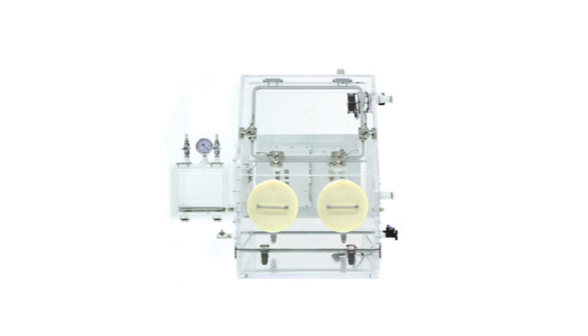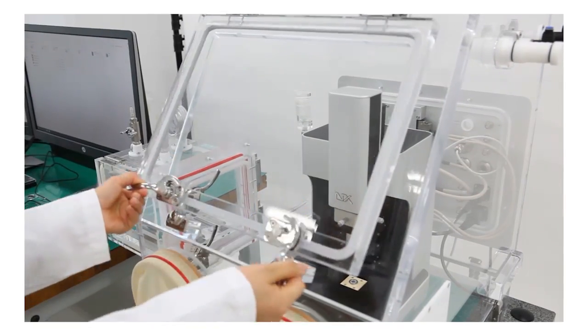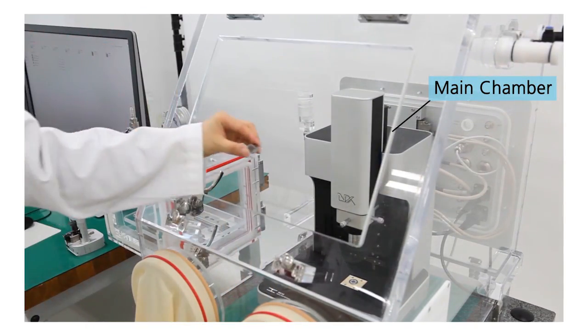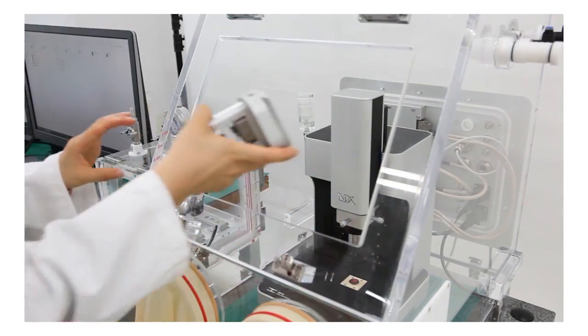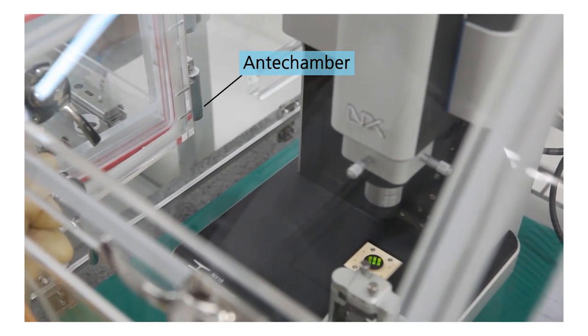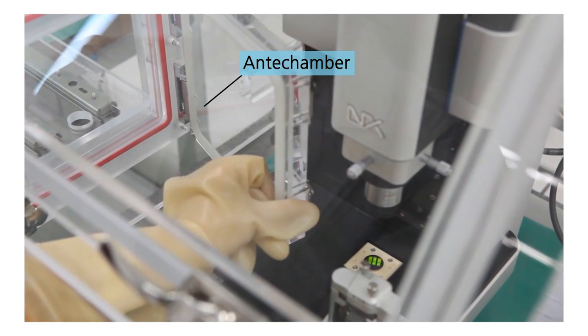Glovebox for Park NX10 is composed of a transparent acrylic main chamber and an antechamber attached to its left wall. The main chamber's door allows you to easily load samples for analysis or to replace the current Park NX10 AFM head. After the chamber environment has been adjusted, the antechamber's door can be used in the same way.